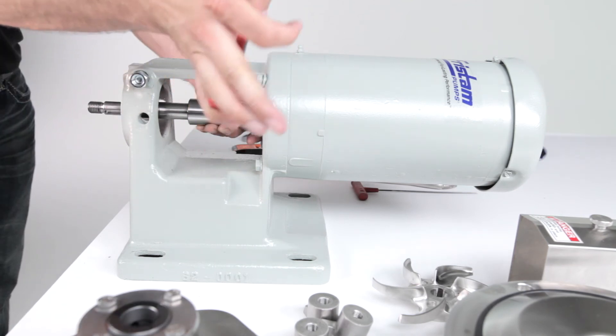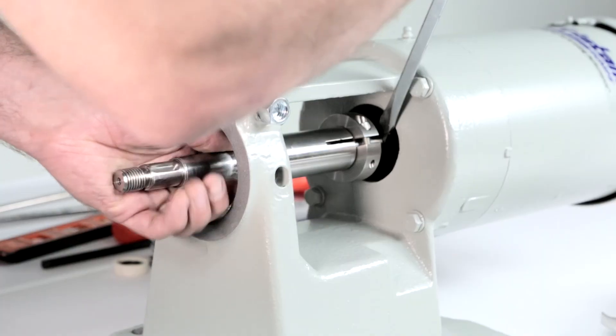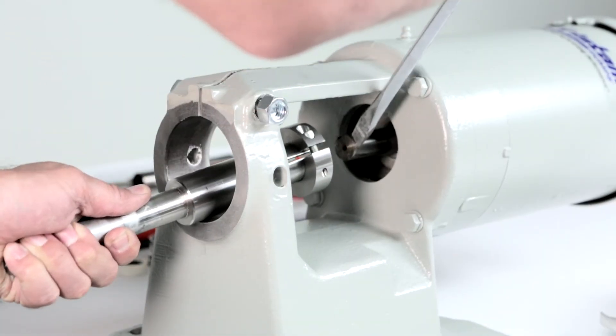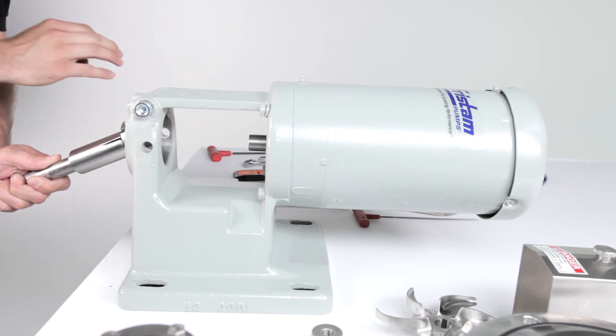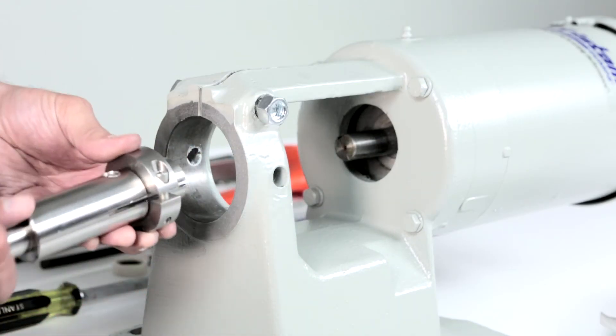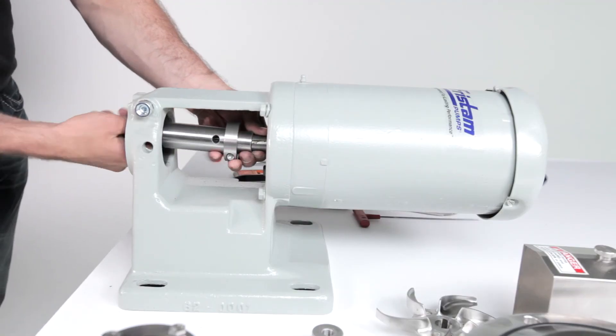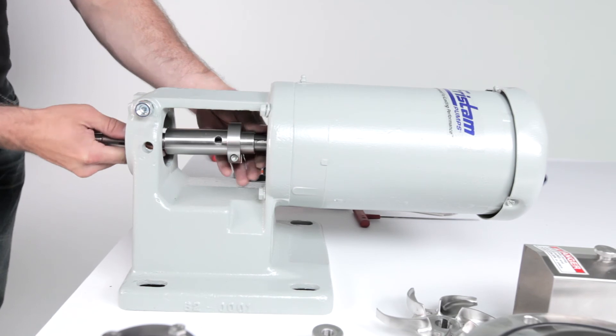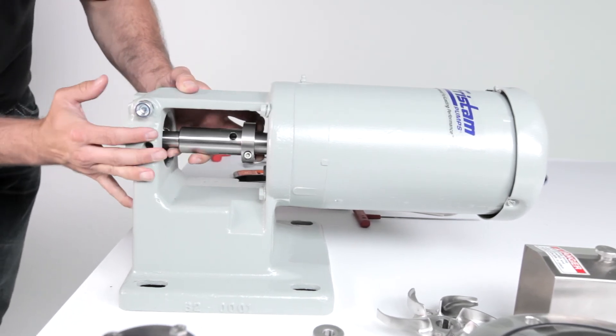Loosen the shaft collar screw on the shaft collar with the Allen wrench. Pull the pump shaft off the motor shaft. To install the new shaft, align the slot of the clamping ring directly over the slot on the shaft. Then slide the new shaft collar onto the pump shaft, but do not tighten the shaft collar screw at this time. Slide the pump shaft and shaft collar onto the motor shaft.